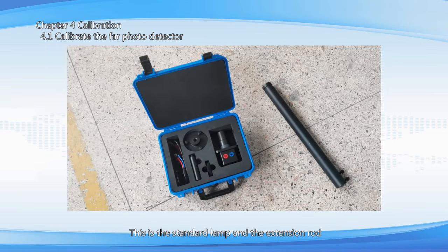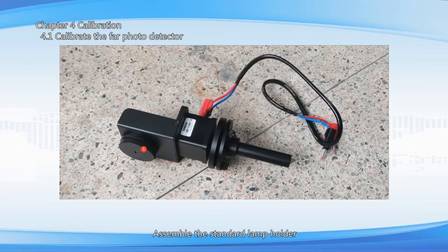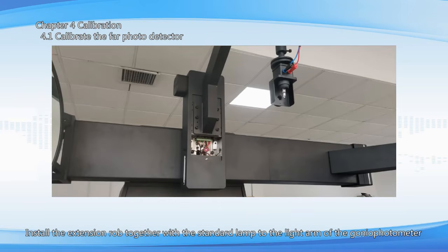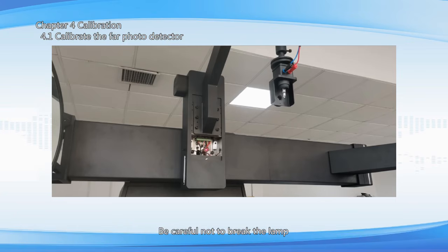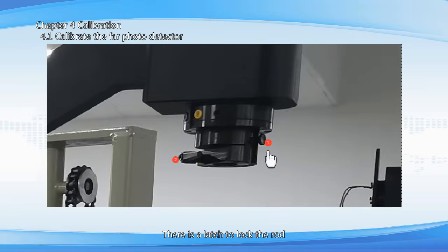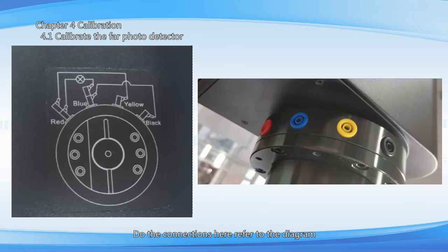This is the standard lamp and the extension rod. Assemble the standard lamp holder. Install the small mirror tool here. Install the extension rod together with the standard lamp to the light arm of the gonio-photometer. Be careful not to break the lamp. There is a latch to lock the rod. And the screw handle to tighten the rod. Do the connections here, referring to the diagram. This connection method is not only for the standard lamp but also for the samples in future.